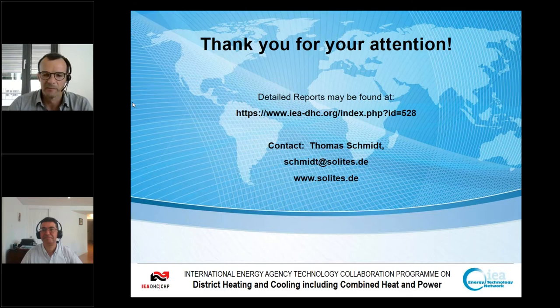So we have been doing this work for quite a lot of time, many years. We have a lot of experience with simulated load predictions and also with monitored load predictions. What we also normally do, if we have the system simulation, is easily make a sensitivity analysis and vary the load in the amount of heat that has to be delivered, as well as in temperature levels. Then we can see how sensitively the entire system reacts on a variation of, for example, load conditions and also other weather conditions. So here, the system simulation is a very good instrument to get more confidence in the design of the entire system.